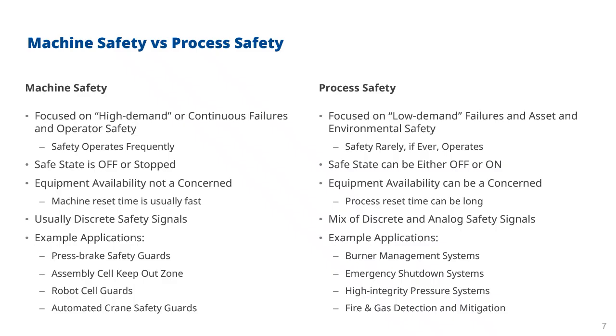Let's compare machine safety versus process safety. So machine safety is covered under the EN ISO 13849 standard, along with other standards. And generally machine safety is focused around protecting the operator from harm. So typically this is focused on high demand or continuous failures and operator safety, where the safety operates frequently. So for example, imagine that you have an operator that's loading a machine with components. The machine then performs an operation, and then the operator unloads those components. So that might be happening every few minutes or even every few seconds. So each time the operator puts their hand in, the machine needs to be in the safe state to prevent operation and leading to potential crush injuries. So that's one aspect of that machine safety.